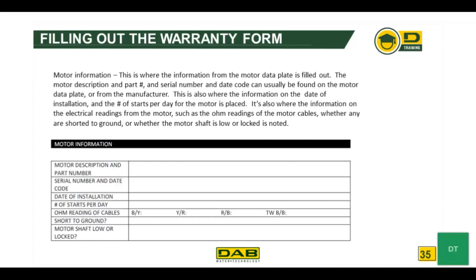This is where the information on the date of installation, the number of starts per day, and the like for the motor is placed. It's also where the information on the electrical readings from the motor, such as the ohm readings of the motor cables, whether any are shorted to ground, or whether the motor shaft is slow or locked, is noted. Note that some of this information can be filled out when the motor with the pump is installed, but some of it will have to be filled out afterwards.